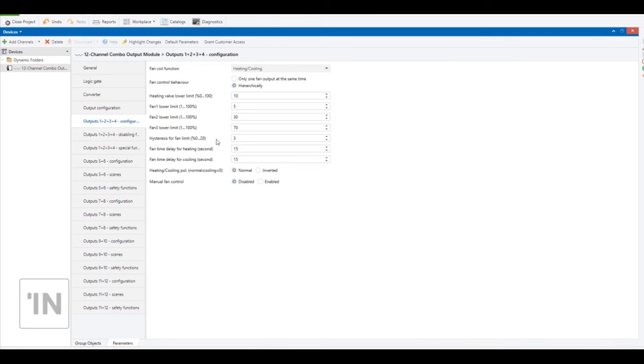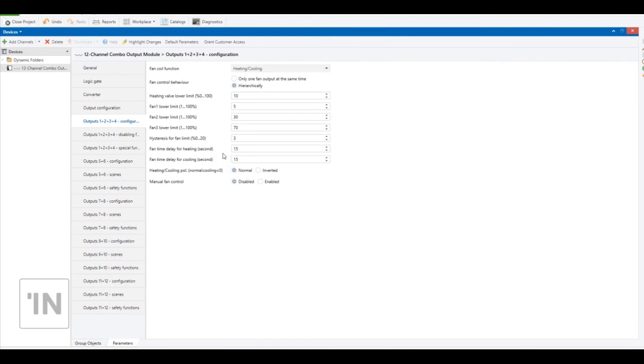Fan time delay for heating and fan time delay for cooling: this parameter sets a delay time between the opening of the heating or cooling valve and the fan switching on. After the heating or cooling valve is opened, it waits for this delay time, and after that time it turns on the fan.